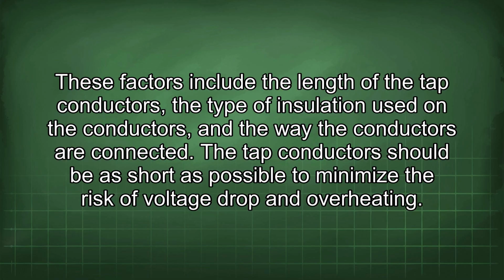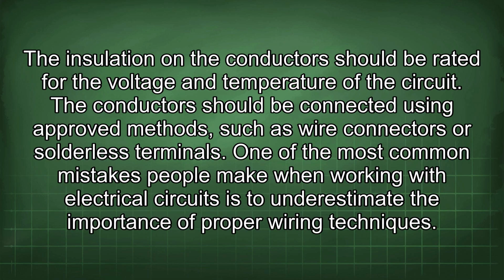The tap conductors should be as short as possible to minimize the risk of voltage drop and overheating. The insulation on the conductors should be rated for the voltage and temperature of the circuit. The conductors should be connected using approved methods such as wire connectors or solderless terminals.